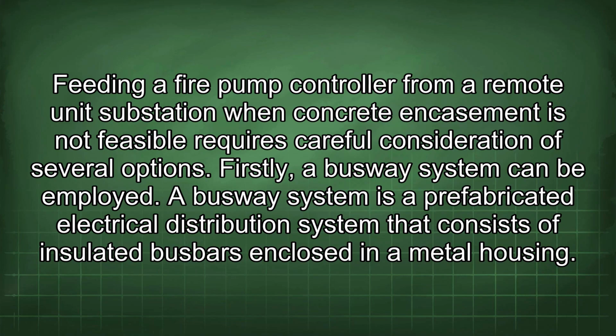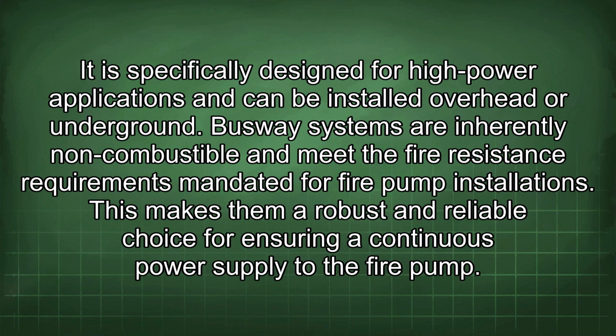Feeding a fire pump controller from a remote unit substation when concrete encasement is not feasible requires careful consideration of several options. Firstly, a busway system can be employed. A busway system is a prefabricated electrical distribution system that consists of insulated bus enclosed in a metal housing. It is specifically designed for high-power applications and can be installed overhead or underground.